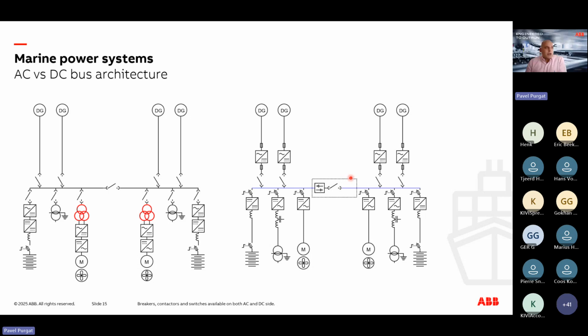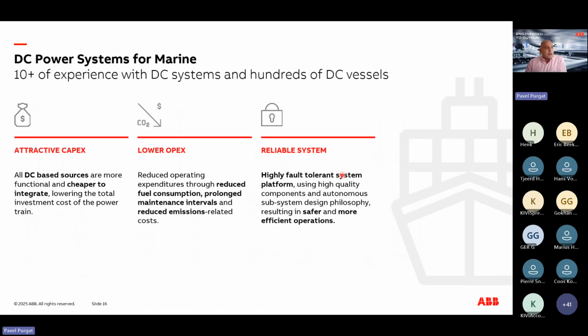Of course, what you need to think about is the protection. But already here we can see that we will probably be using the traditional protection devices. We have the fuses, we have switches, switch disconnectors, but also some new devices that I will be talking about later. So what the colleagues in marine showed over the last 10 years, or actually more, because the first DC vessel was released in 2013 by ABB, and it was Dina Star. And in that time, the DC systems in marine became often cheaper to acquire. They are for sure cheaper to run because of the fuel economics. And they proved to be more reliable because the system design is quite new and because the number of components is reduced.